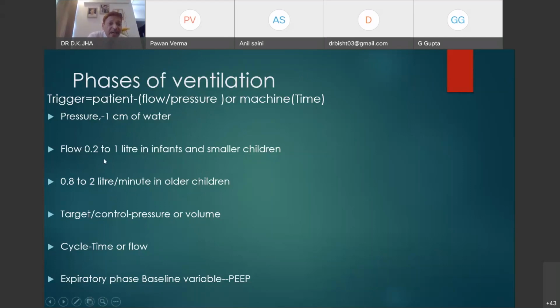So the sensitivity of the trigger should be set so that the breath by the machine is delivered accurately and at an accurate frequency. If you have set the trigger too small, the machine will sense early, and more breaths will be delivered by the machine, causing high-frequency ventilation, which is dangerous to the patient. If you have set the sensitivity very high, like 2 centimeter, 10 centimeter, then the machine will wait for the pressure to generate and it will not deliver the breath. So there will be hypoventilation. So the trigger should be selected cautiously. If you are selecting a pressure trigger, set at this; flow trigger, set at this.